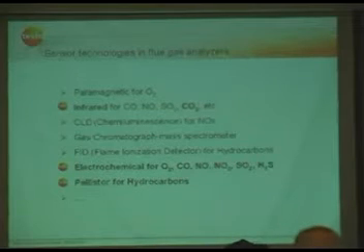You have a CO2 max, but this CO2 has been calculated in the past, which was okay if you don't have materials which absorb CO2 during the burning process. That means if you have a small burner and you would like to get the CO2 reading, you can use a calculation.